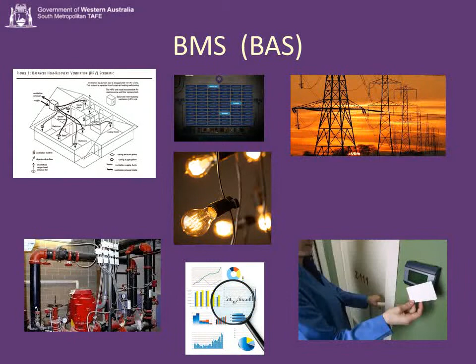The first thing they started doing was controlling the air conditioning. Because it was a big networked system with everything talking to everything else, the air handling units could talk to the rooms and ask how they were doing, what the temperature was, and alter their behavior depending on how the rooms were controlling or whether the room was occupied. Then the air handlers could talk to the chillers, which would start when the air handlers needed cold water, or the boilers would start when hot water was needed.